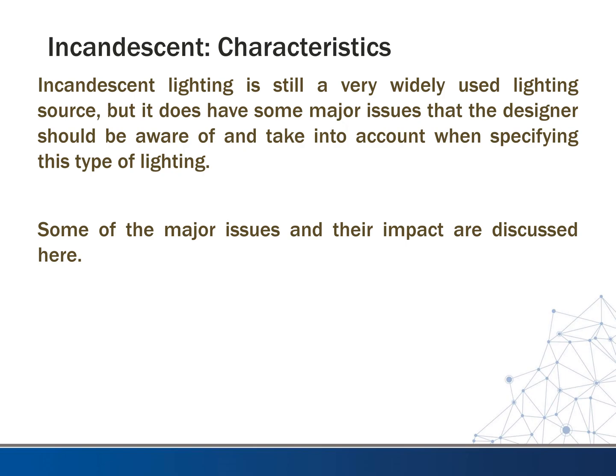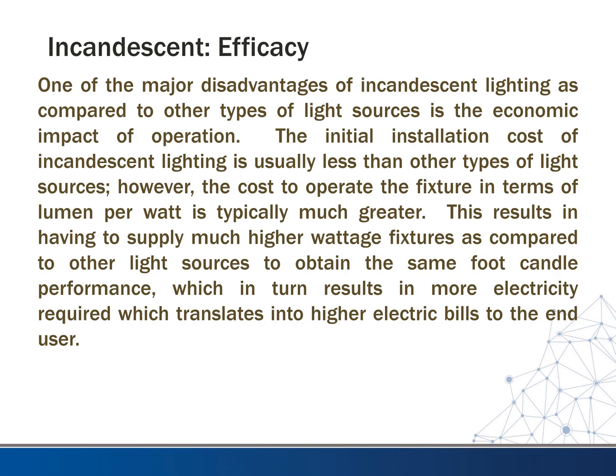Some of the major issues and their impact are discussed here. One of the major disadvantages of incandescent lighting compared to other light sources is the economic impact of operation. The initial installation cost is usually less than other types, however the cost to operate the fixture in terms of lumens per watt is typically much greater. This results in having to supply much higher wattage fixtures to obtain the same foot-candle performance, which in turn requires more electricity and a higher electric bill to the end user.